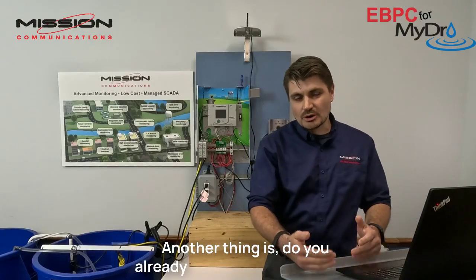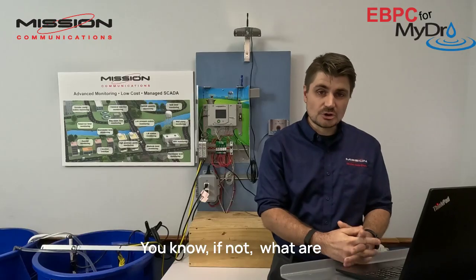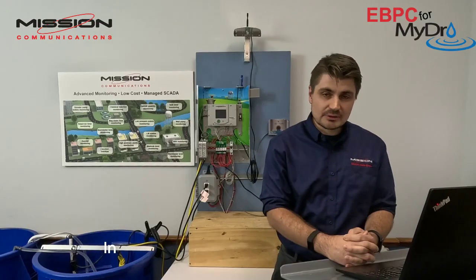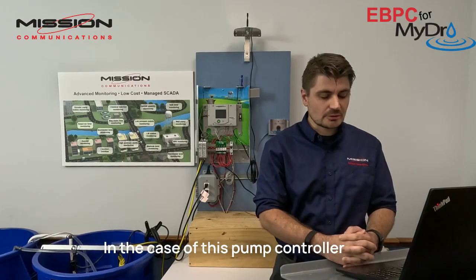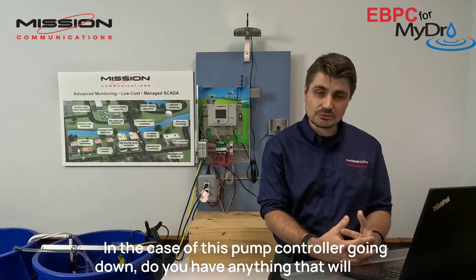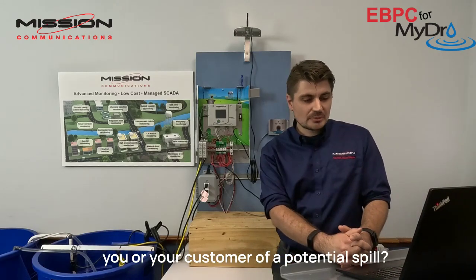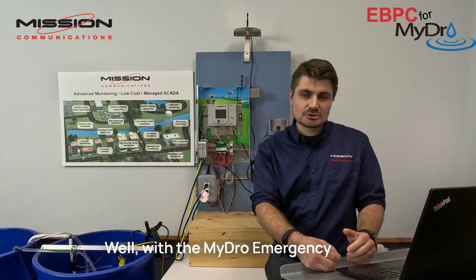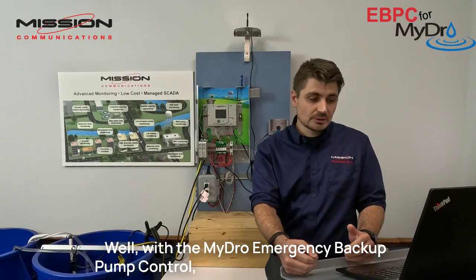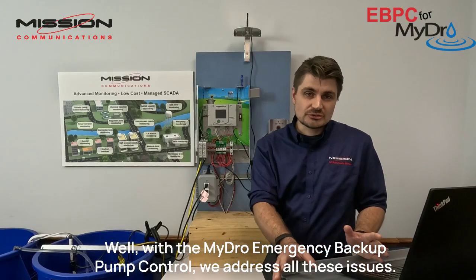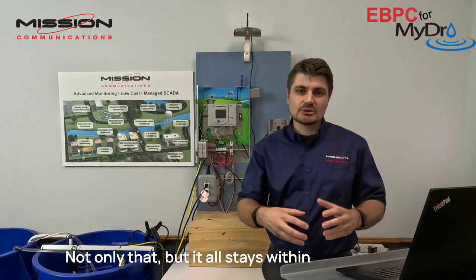Another thing is, do you already have a backup in place? If not, what are you going to do to prevent a spill? In the case of this pump controller going down, do you have anything that will notify you or your customer of a potential spill? Well, with the MyDro emergency backup pump control, we address all these issues. Not only that, but it all stays within your 123 SCADA portal.